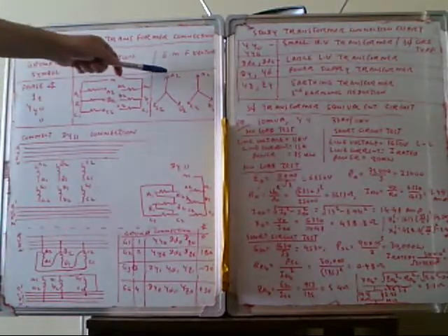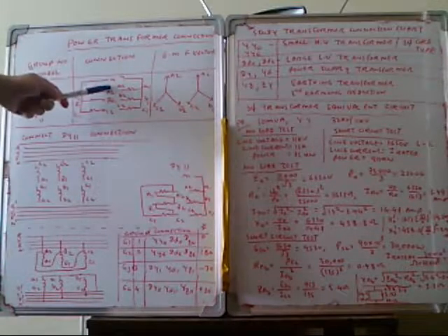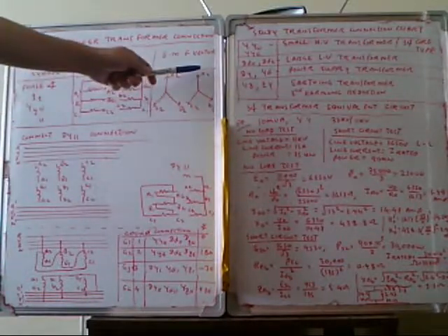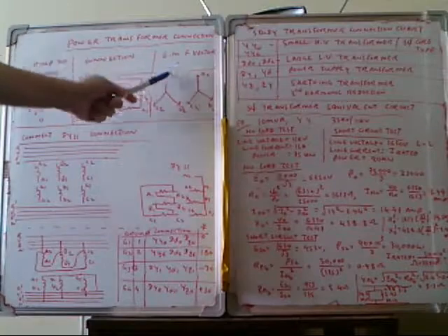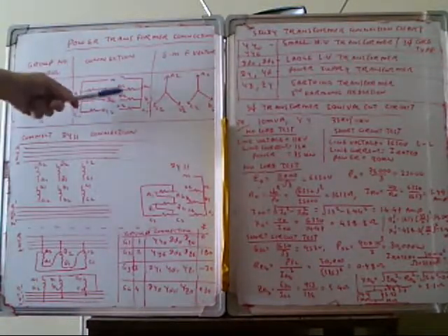In this case, our primary voltage winding vectors A2, B2, C2 and the secondary voltage winding vectors small a2, b2, c2 are parallel. Therefore, the phase difference is 0. So we can write this connection as YY0. This is the typical connection.